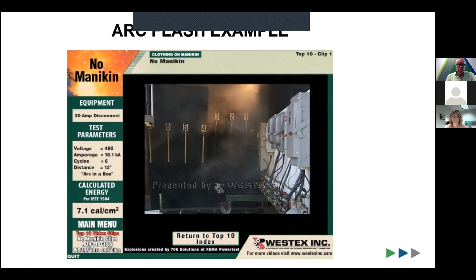Here comes the arc, and within the first couple of frames it's 3 feet out of the box. Again, you're not safe at 18 inches. The arc continues to grow, projects out 6 feet, and begins to put out a massive amount of molten metal, which presents its own hazard - molten metal being in the neighborhood of 1900 degrees Fahrenheit, and non-FR cotton igniting at less than 800.